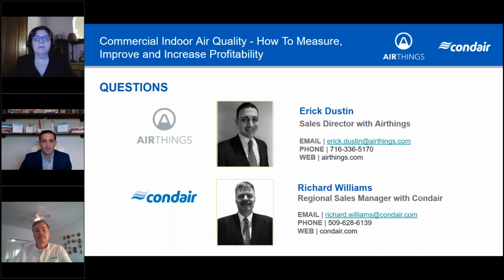Rick, what is the reason for short absorption distance from the distribution head? Another good question. One of the concerns that people will generally have with a direct humidification system is they see the water being atomized directly into space, they worry about dripping and water falling out over, whether it's machinery or over people, over walkways.